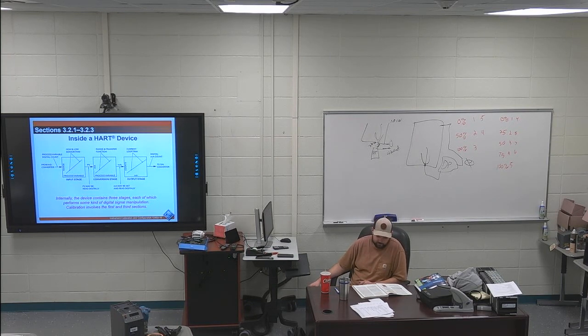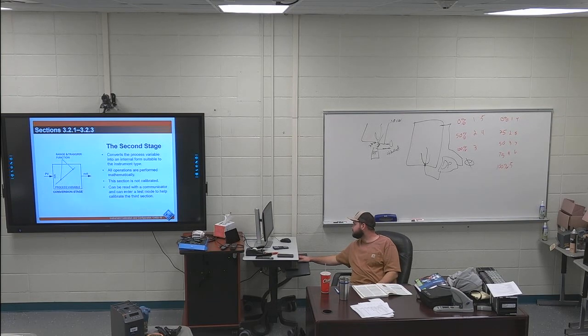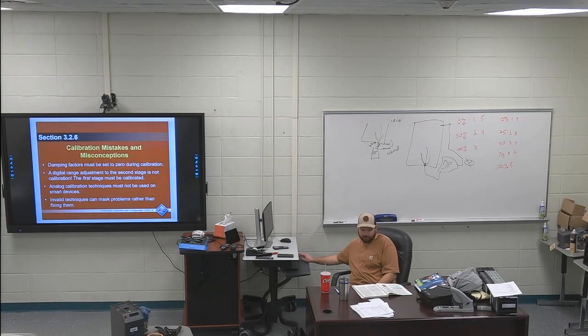Page 23, 326. Test and calibration considerations. This is just factors taken into consideration when calibrating HART devices. I've got the first sentence of dampening highlighted, or damping. Damping. Some HART devices support a damping parameter that causes a delay between the change in the device input and the detection of the change for the output from the device.